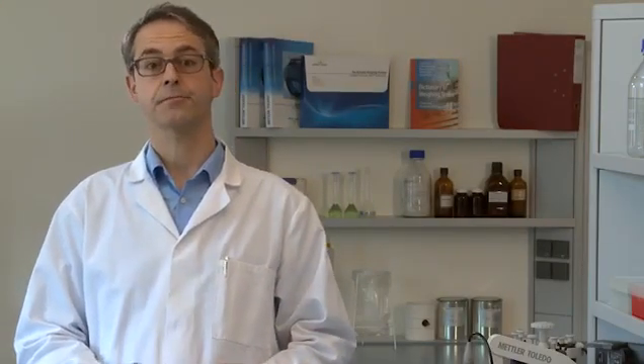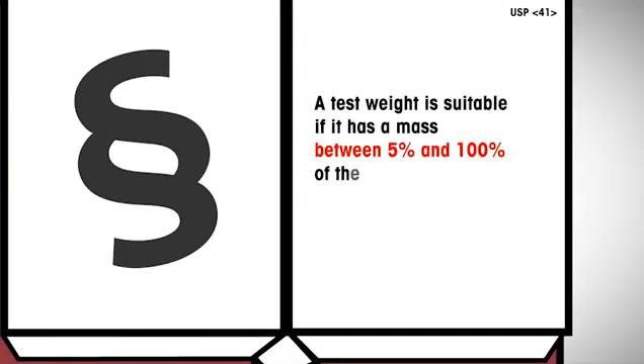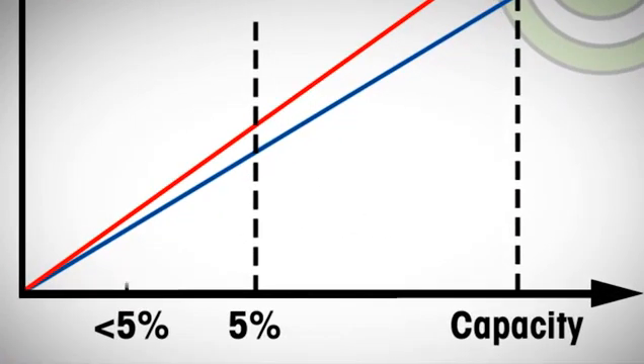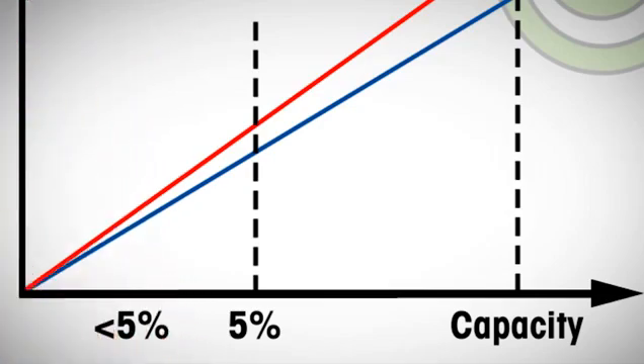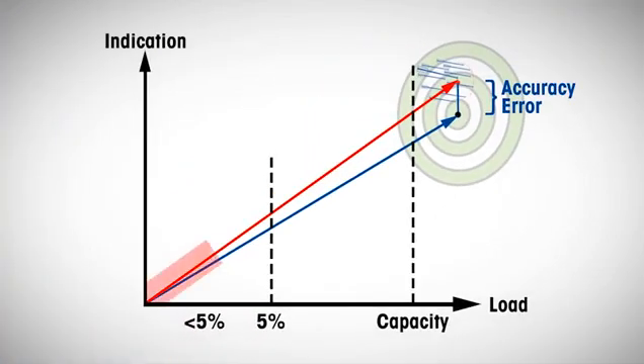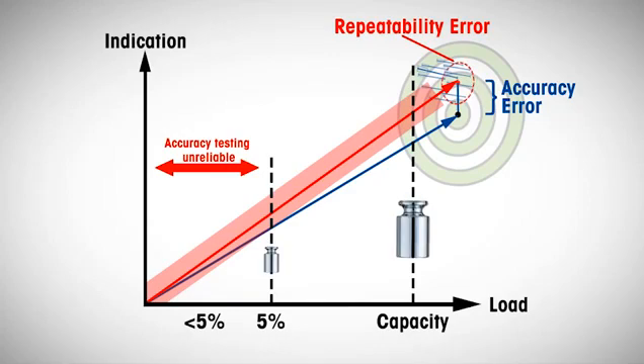So what test weight should be used for accuracy testing? A test weight is suitable if it has a mass between 5% and 100% of the balance's capacity. Note that the current widespread practice of accuracy testing with small weights at the working point is not allowed anymore. At this lower end of measurement range, repeatability is the dominant error and dwarfs the corresponding accuracy error. Hence, for reliable testing of accuracy, a weight between 5% and 100% of the capacity must be used.